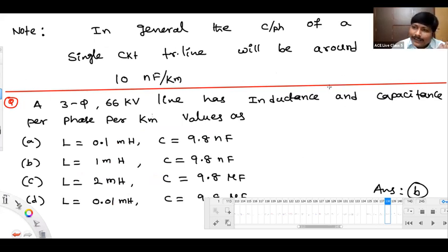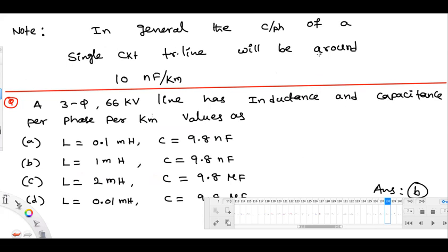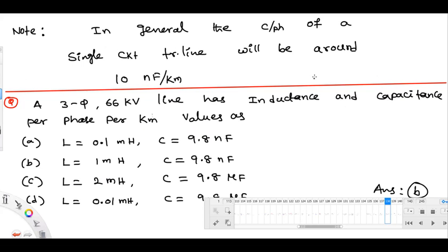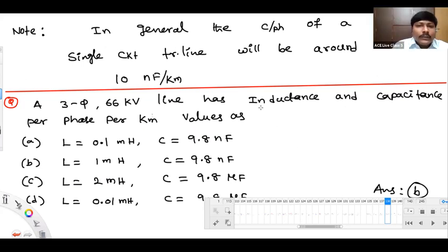I discussed at one point the inductance value by the same meaning of GMD by GMR variation. It won't have a great value variation. It will be coming in the range of 1 to 1.2 millihenry per kilometer as a conclusion. Similar to capacitance, the inductance value will have some range per kilometer. Just check back.